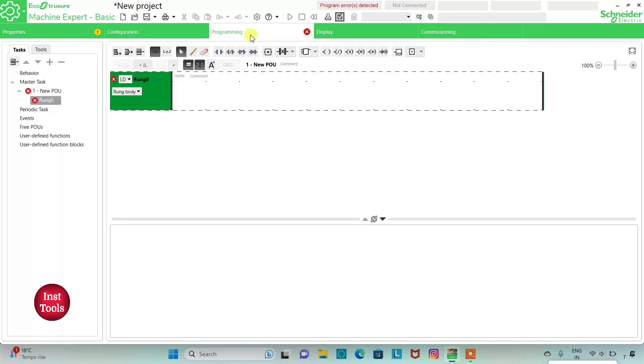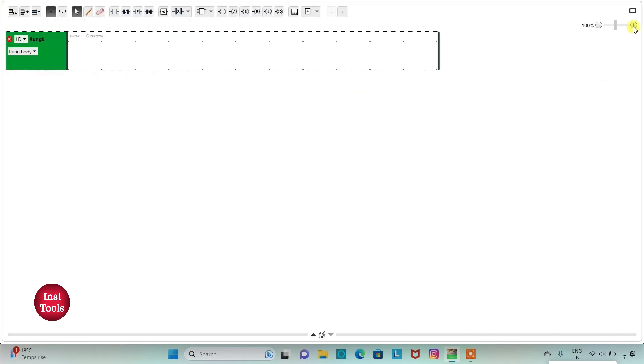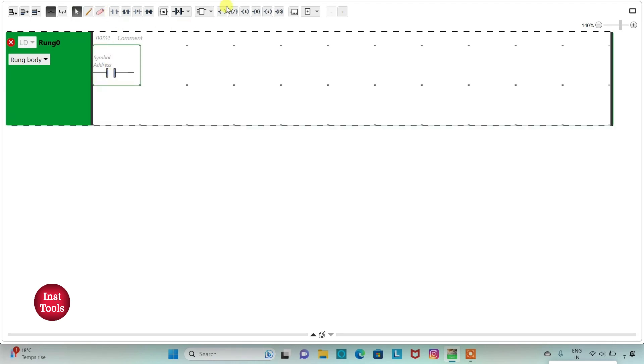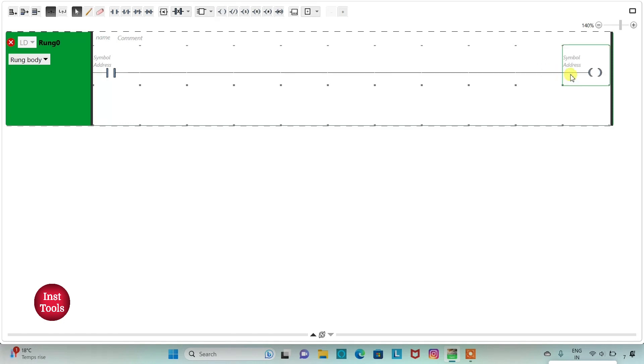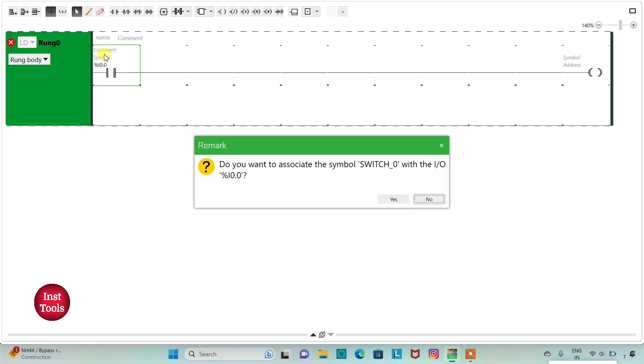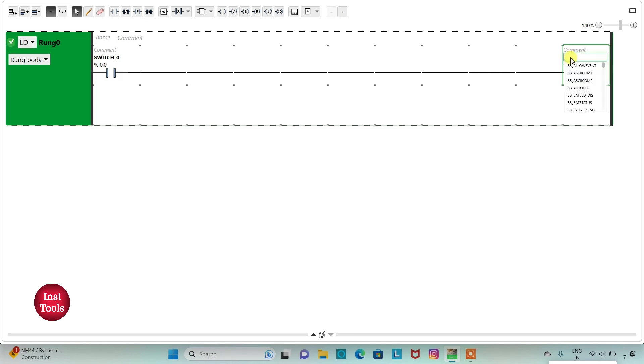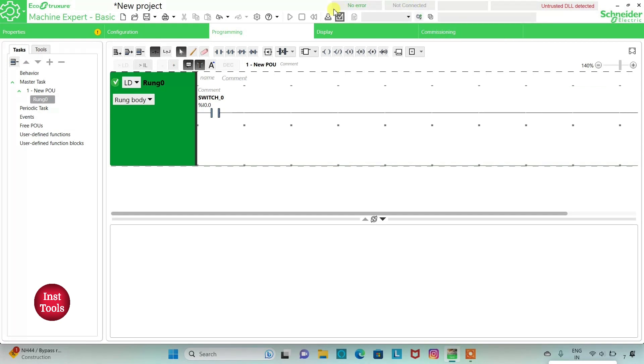Then I will go to the Programming tab where we will draw the ladder diagram for latching. I will click on full screen mode and zoom in. I will insert a normally open contact and assign the address as I 0.0 with symbol Switch 0. Then I will assign the address to the coil as Q 0.0 with symbol Output 0. We will exit full screen mode and compile the program.